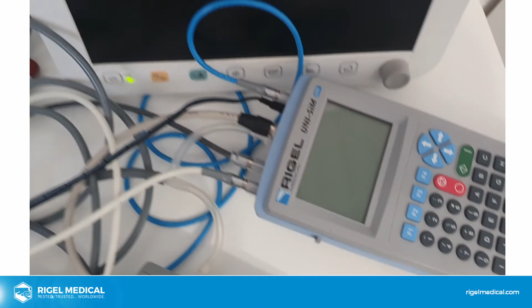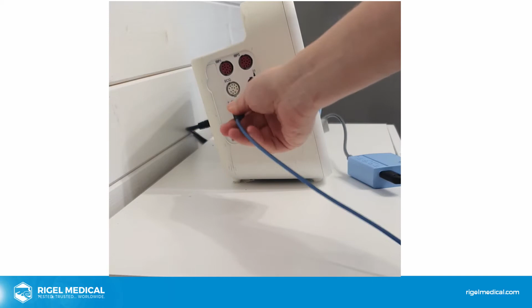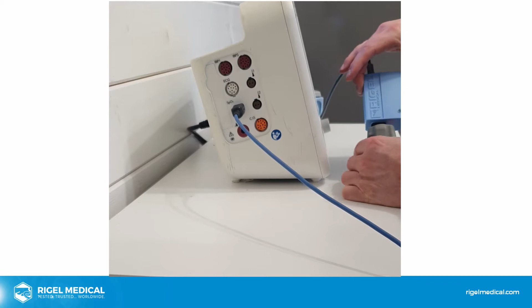And now let's have a look at the side of the patient monitor. So firstly we plug in the SpO2 cable, so start with that one for the patient connections. Make sure the patient monitor is on and the Uni-Sim is performing a simulation, just so we can see that the LEDs are lining up. And what will happen on the pulsar is you'll get two blue lights. Make sure they're not flashing. A bit fiddly this part. Okay, so that's okay. That's set up.